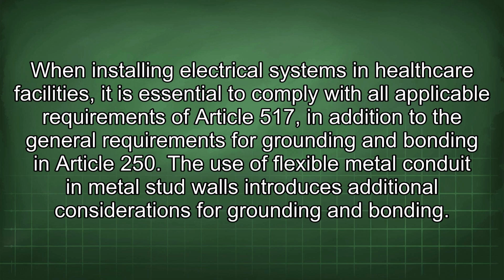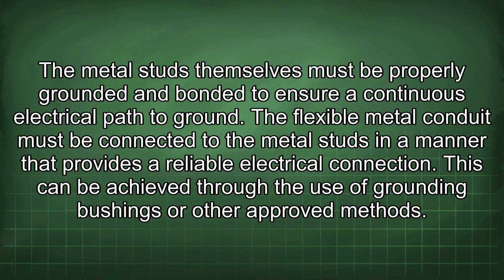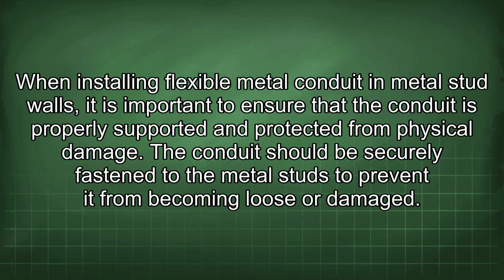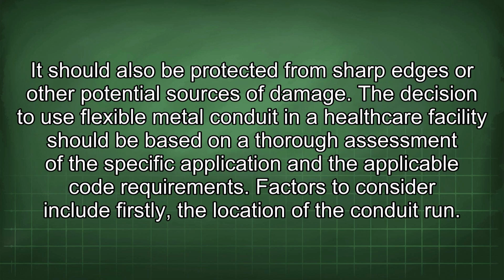The use of flexible metal conduit in metal stud walls introduces additional considerations for grounding and bonding. The metal studs themselves must be properly grounded and bonded to ensure a continuous electrical path to ground. The flexible metal conduit must be connected to the metal studs in a manner that provides a reliable electrical connection. This can be achieved through the use of grounding bushings or other approved methods. When installing flexible metal conduit in metal stud walls, it is important to ensure that the conduit is properly supported and protected from physical damage. The conduit should be securely fastened to the metal studs to prevent it from becoming loose or damaged. It should also be protected from sharp edges or other potential sources of damage.